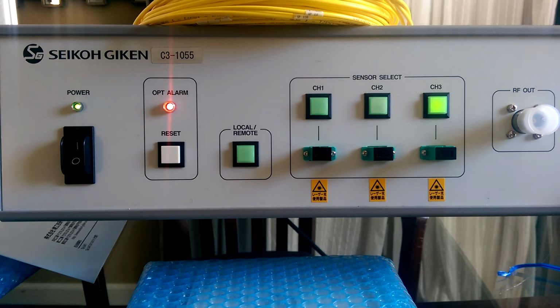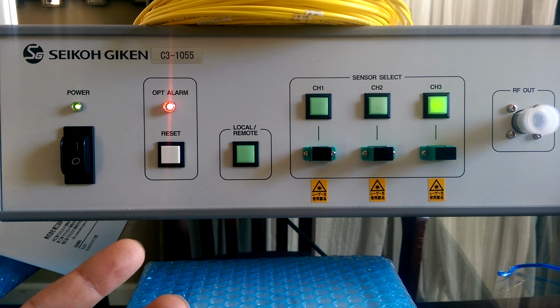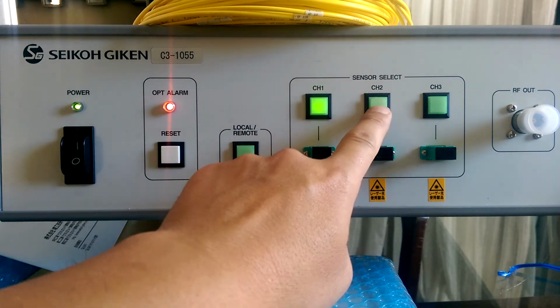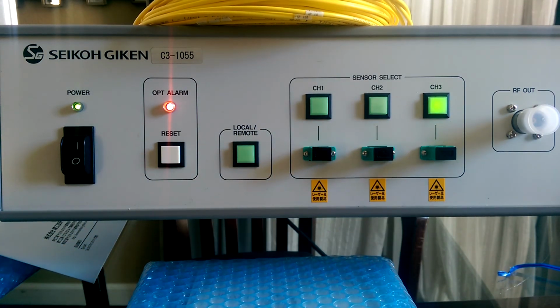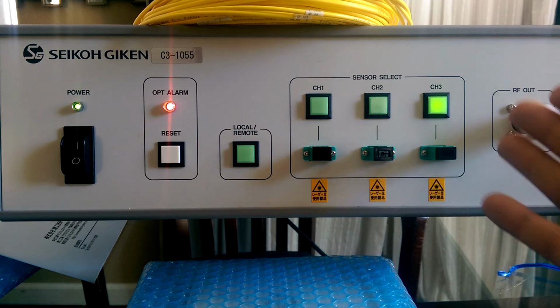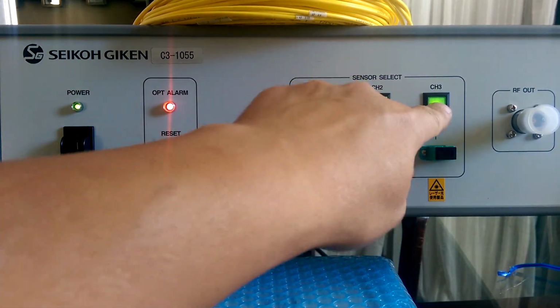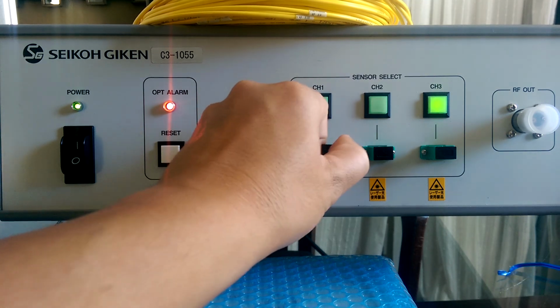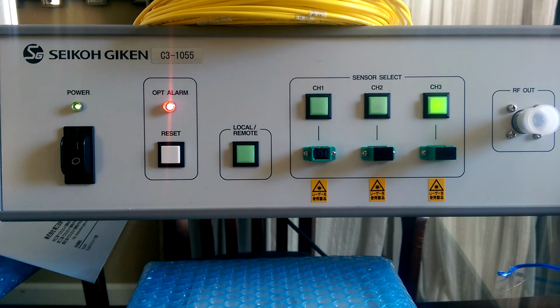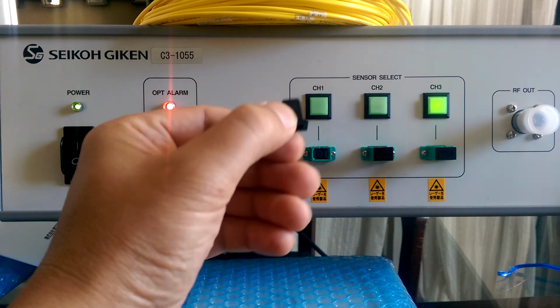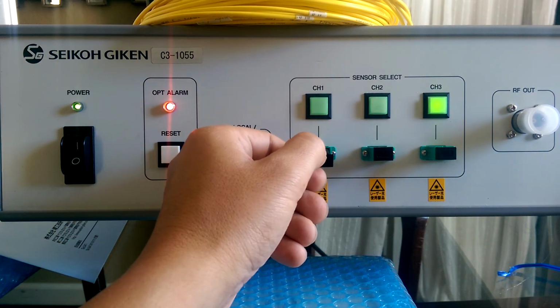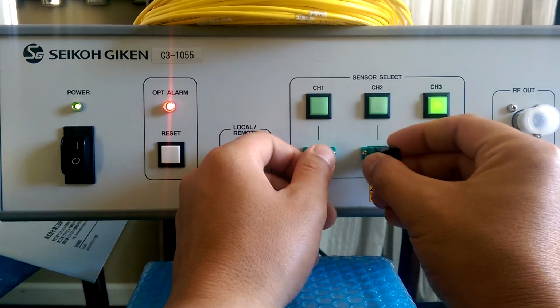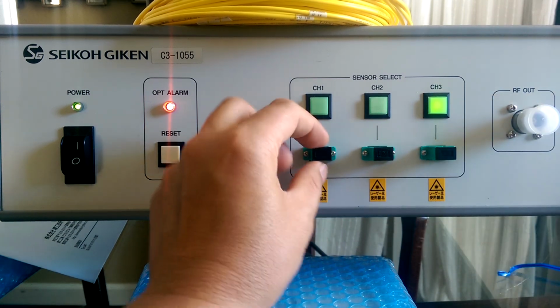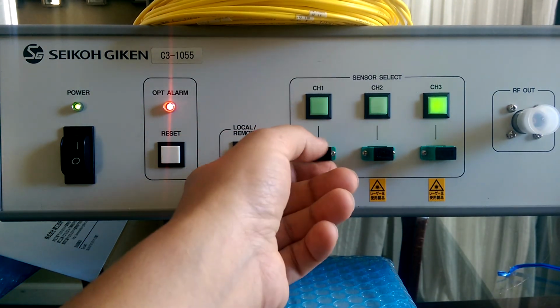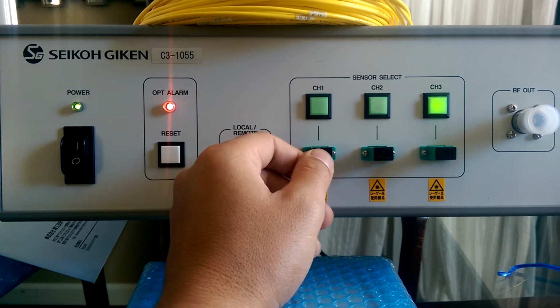It's pretty straightforward. If you don't want the automated process and you're testing 3 channels, you can manually switch between channels on the front panel in the sensor select section. You also have the adapters where your fiber connects for each channel. This is a dust cap - each channel has one. Please, when you're not using the system, keep the dust caps in to keep debris or dust from getting the adapters or connectors dirty.